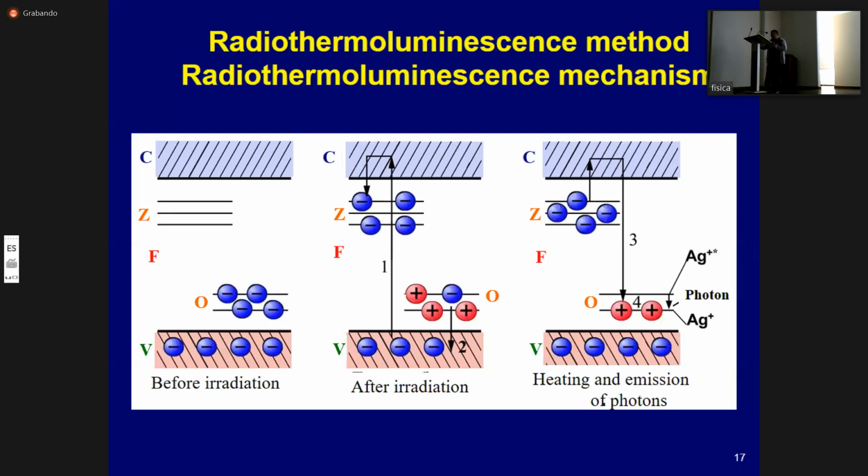A distinctive feature of the luminescence is the destruction, during heating, of the centers created under the action of ionizing radiation. So, after the measurement procedure, the thermoluminescent dosimeter loses information about the radiation dose and can be used for the next user.